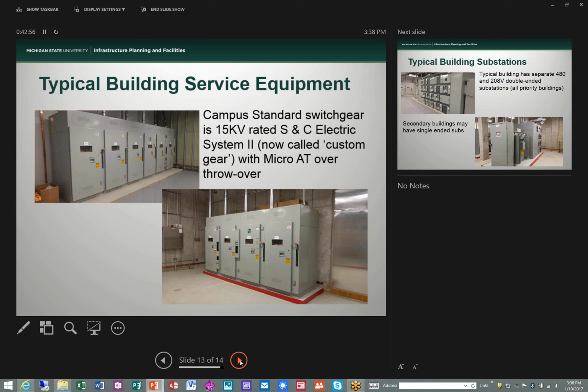Directly upstream of this gear that we're looking at, do those 2 incomers ultimately start from the generator buses that we thought, the 6 generator buses, or 2 of those 6 generator buses? The next overcurrent protection device north of those 2 switches on the left end are in fact the distribution breakers on the plant buses in the plant. Is there some switches between, or not, like non-protected? No switches in between.